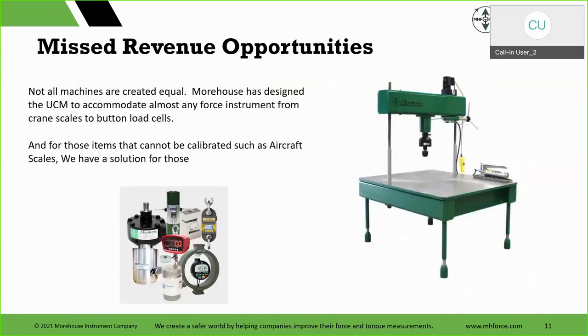In addition, missed revenue opportunities. Here we put in our scale press. This is on UCMs, but we have a scale press. It's designed to calibrate scales. The universal calibrating machine was designed to do tension links, crane scales, almost anything we could throw at it. But if we made it to do scales, that machine would get so big and take so much steel and get so costly. And it's just not a good design to make a UCM that's as big as a scale press. So this on the right is for aircraft scales. That is a difference. The cal machine can do some scales, but it's very limited with the footprint that's on it. So if you want to get the scales from all the manufacturers, GC, Intercomp, all of those, the big aircraft scales, the big thing there with adapters is to make sure you replicate the tire print.